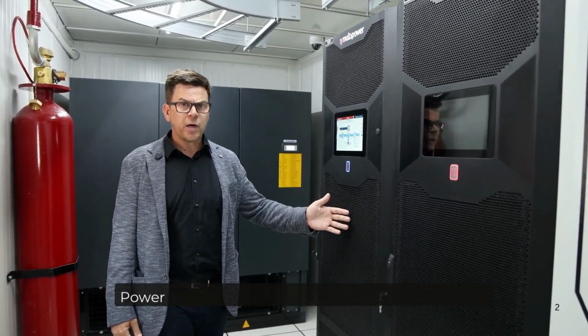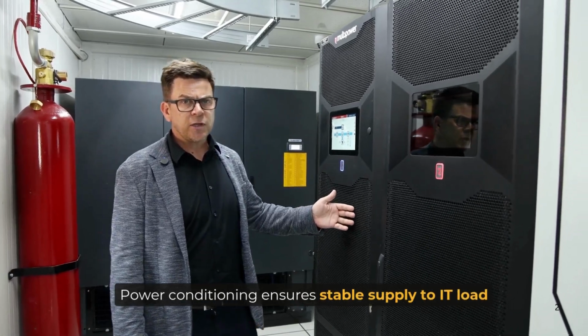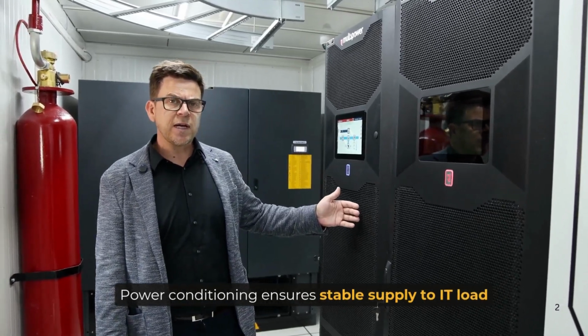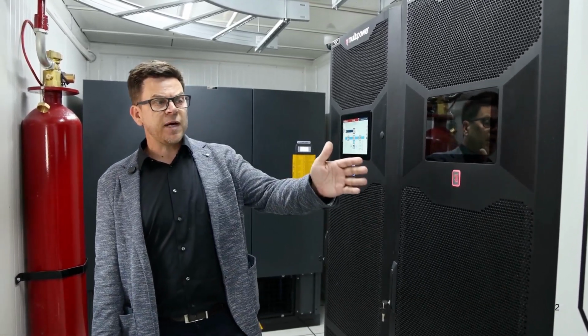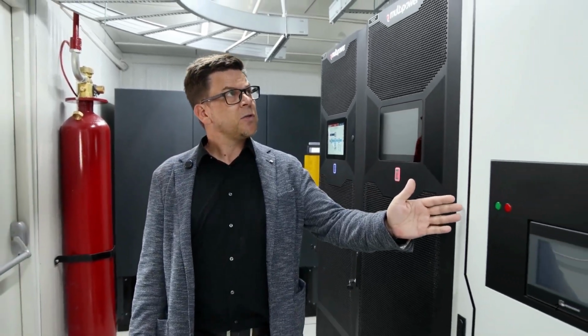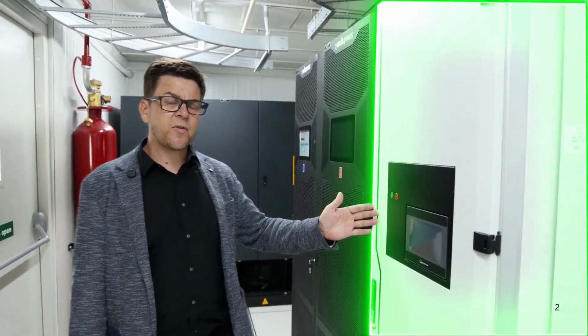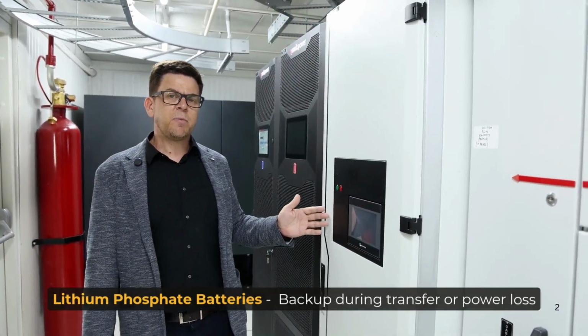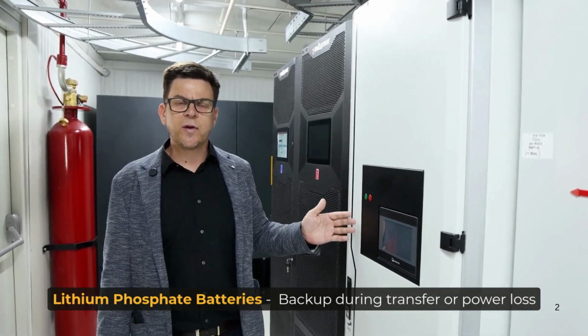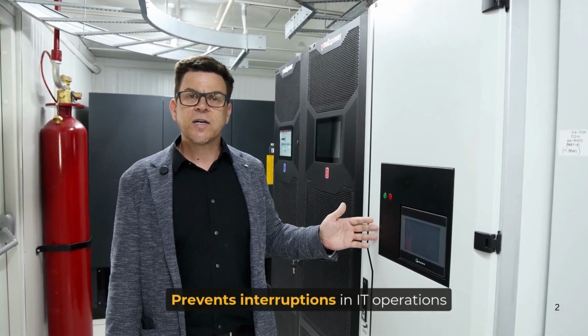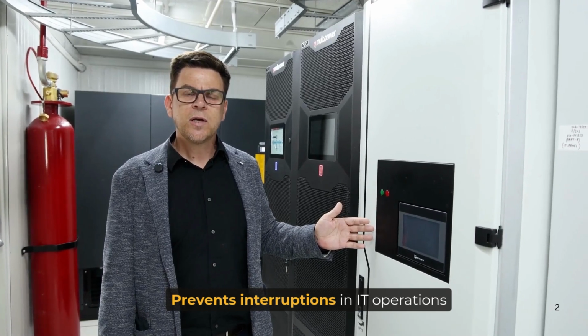This provides all the power quality and power conditioning that would supply the IT loads within the data center, and is then supplemented by the battery cabinets just to the right of the UPS. These are lithium phosphate batteries, providing the backup when you're doing a transfer or when you have a loss of mains power, essential to operation of IT loads so that you're ensuring that there are no interruptions.